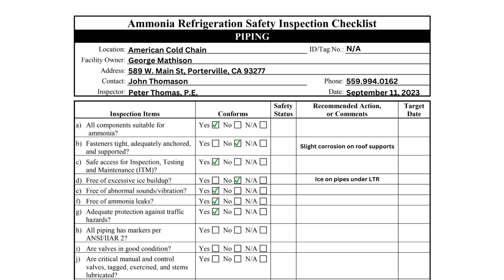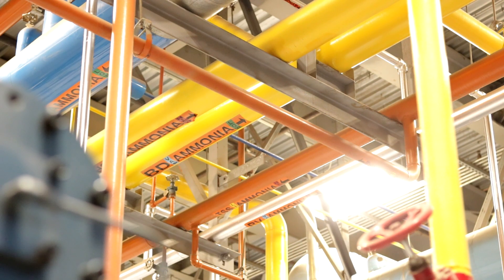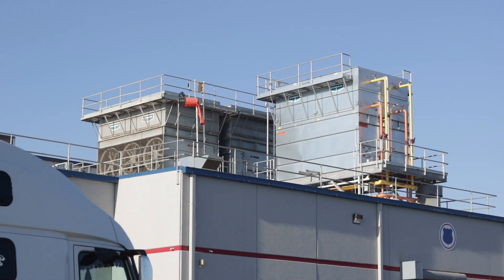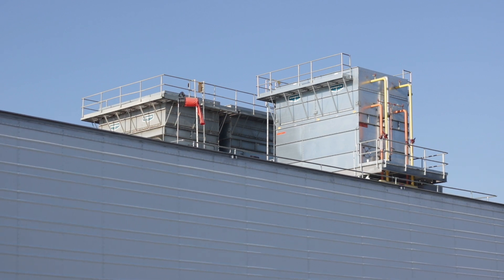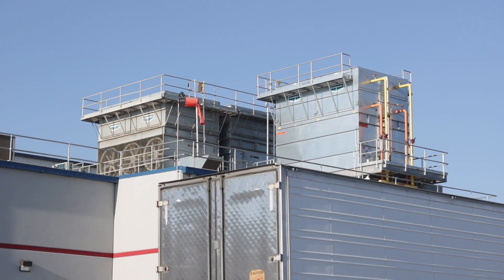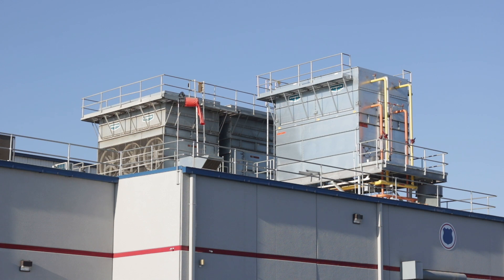Item G asks if the piping is adequately protected against traffic hazards. It is not uncommon for ammonia piping bridges to extend throughout the facility and be located in heavily trafficked areas, where service trucks, forklifts, or semi-trailers could come into contact with live ammonia piping. Therefore, it is important that all piping is adequately protected against traffic hazards.